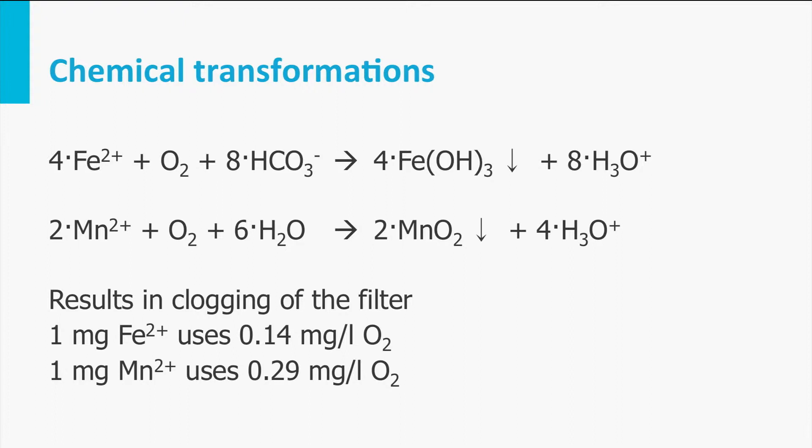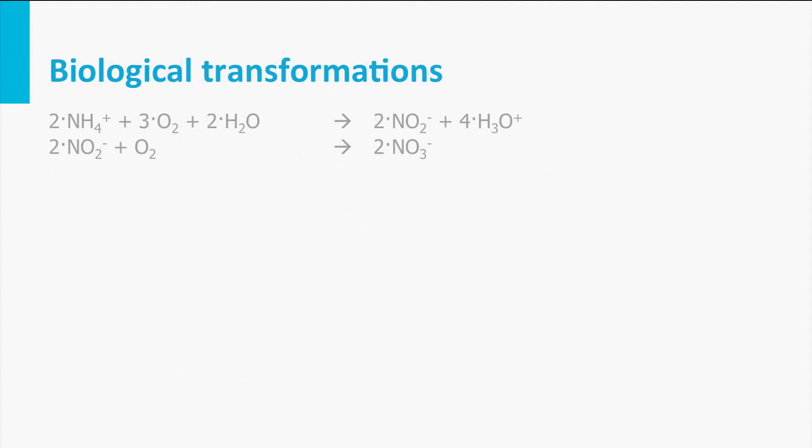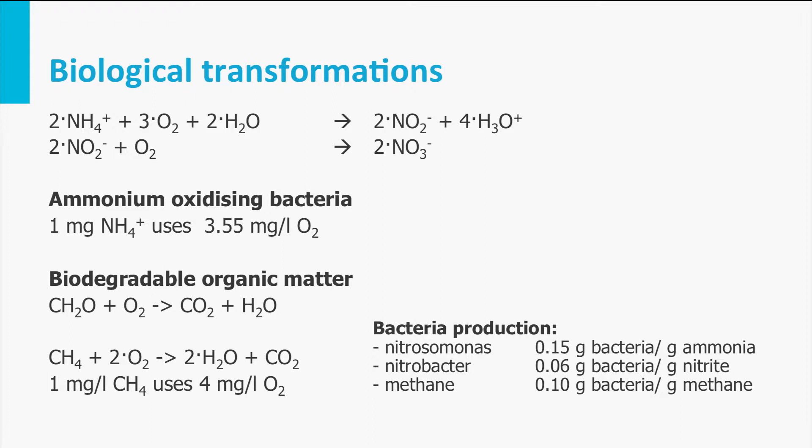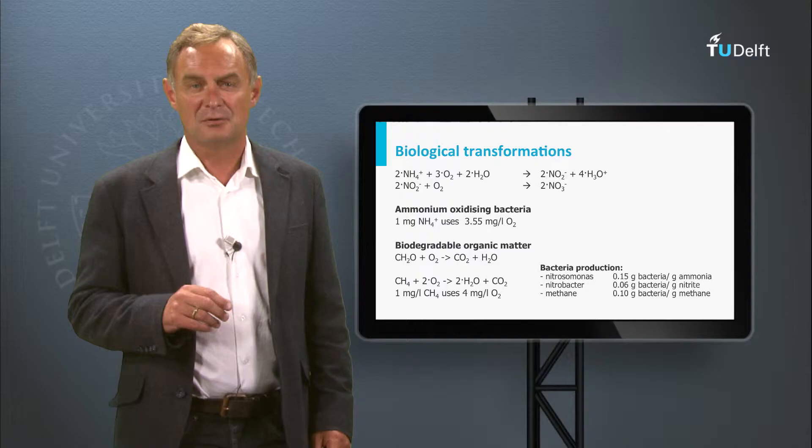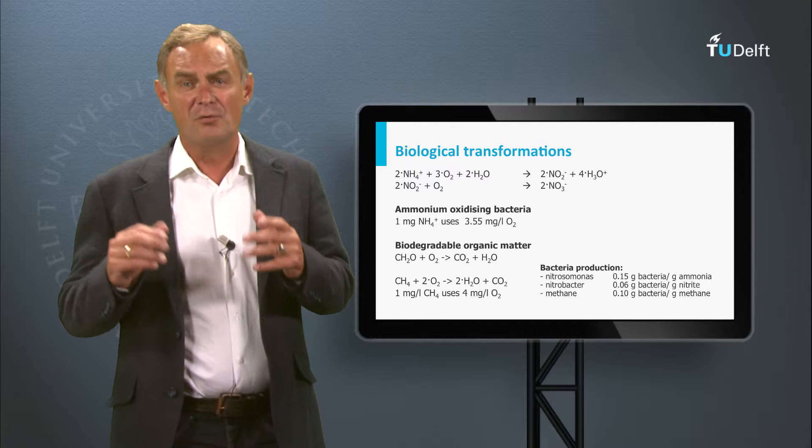Iron and manganese are oxidized chemically and the formed flocs are removed. Ammonia, methane, and biodegradable organic matter can be oxidized by bacteria that are living attached to the filtering material. You can watch an additional movie about this process on the platform.